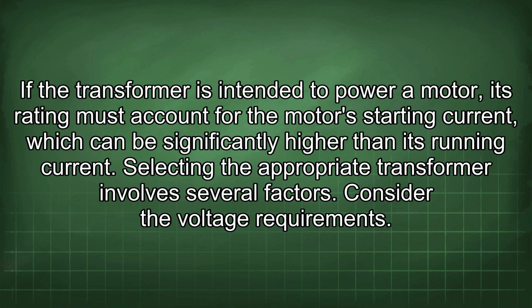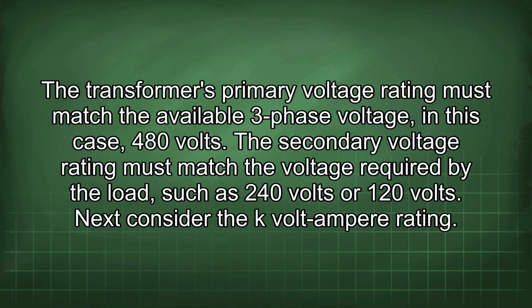Selecting the appropriate transformer involves several factors. Consider the voltage requirements. The transformer's primary voltage rating must match the available three-phase voltage, in this case, 480 volts. The secondary voltage rating must match the voltage required by the load, such as 240 volts or 120 volts. Next, consider the kVA rating.